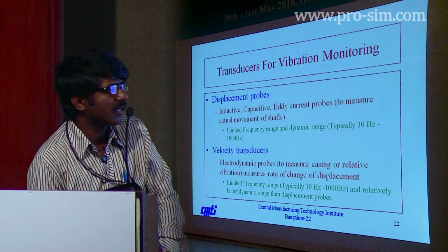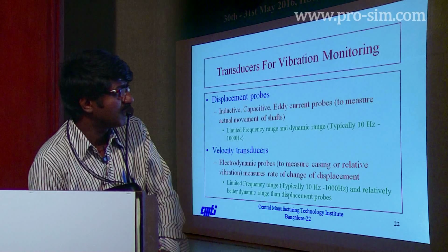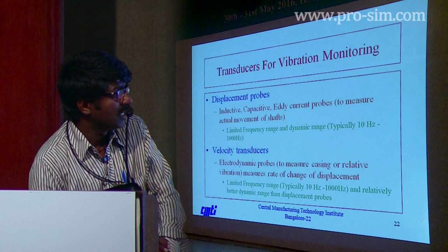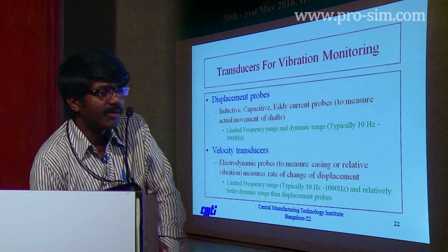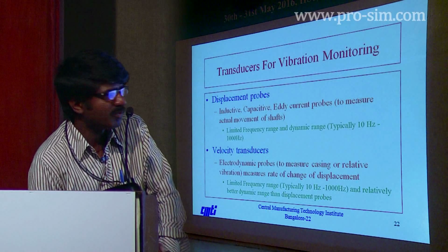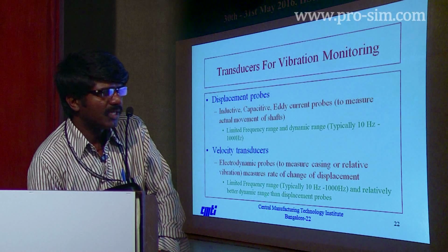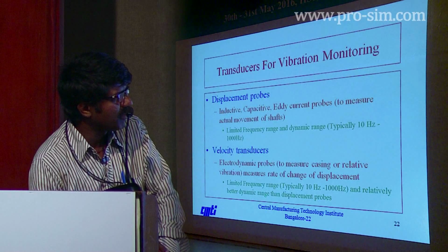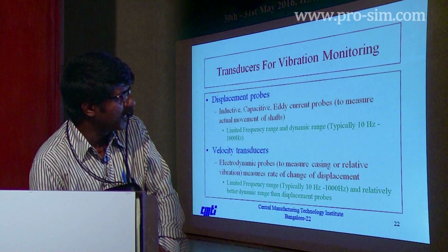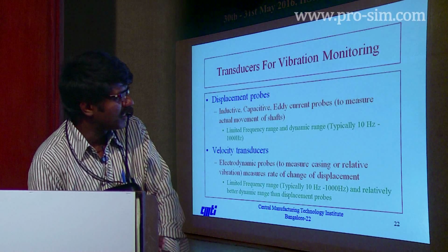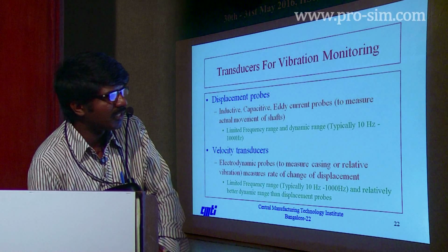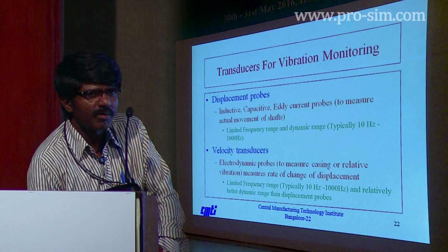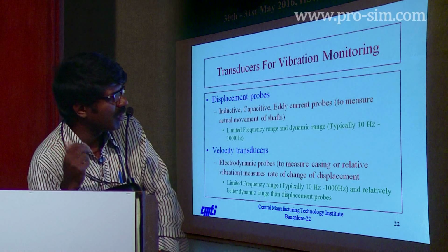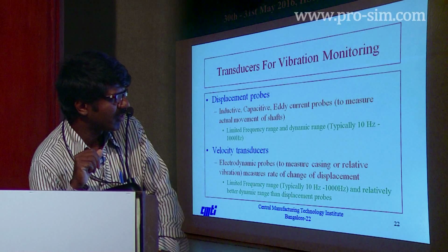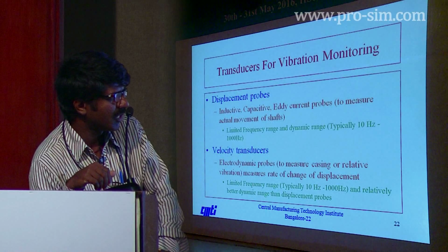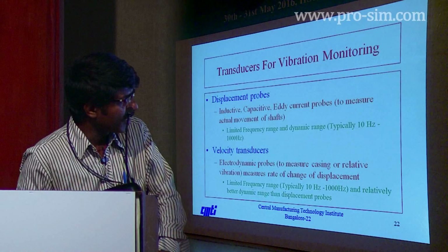Different types of sensors are available. For shaft vibration measurement you can go for displacement probes. In displacement probe itself you can have inductive probe, capacitance probe, eddy current probes. Okay. Only thing is that it has got limited frequency range and dynamic range. You can use it from 10 Hz to 1000 Hz. Next is the velocity transducer. Earlier people were using this transducer. Because of some drawbacks nowadays people are not using it, because it is quite bulky and it has a limited frequency range of 10 Hz to 1000 Hz. So nowadays people are not using this.